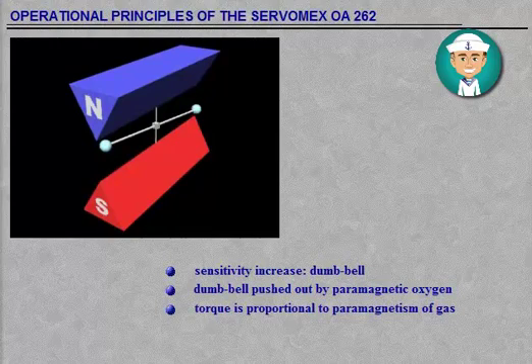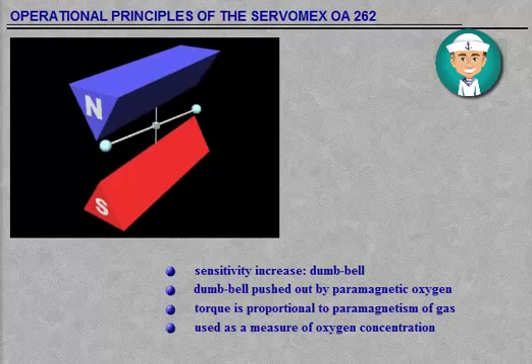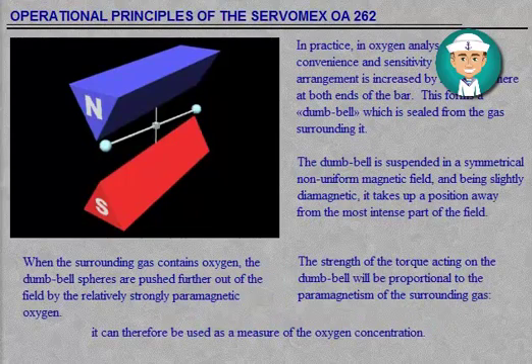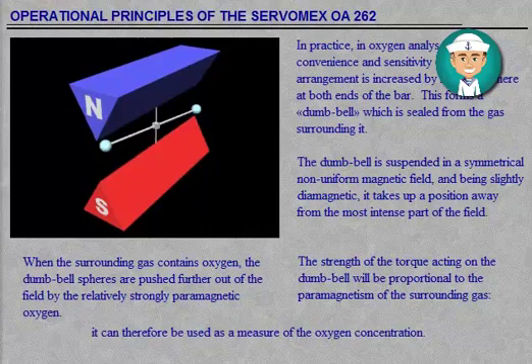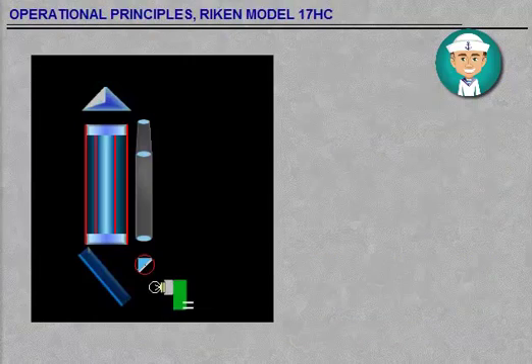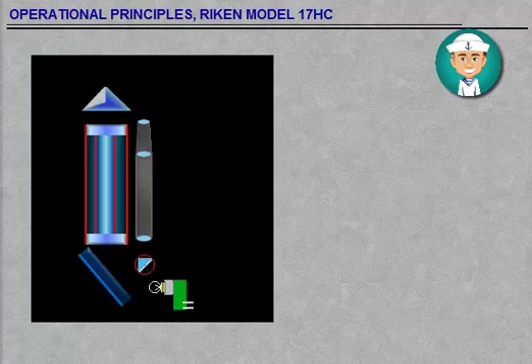The strength of the torque acting on the dumbbell will be proportional to the paramagnetism of the surrounding gas. It can therefore be used as a measure of the oxygen concentration.